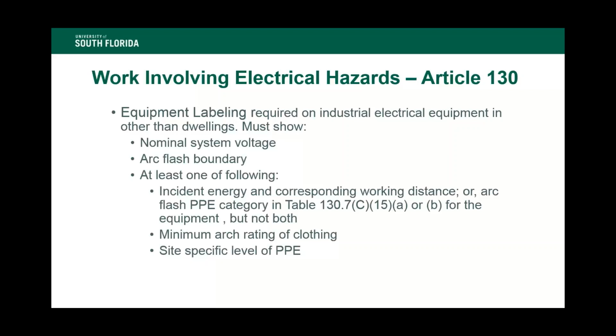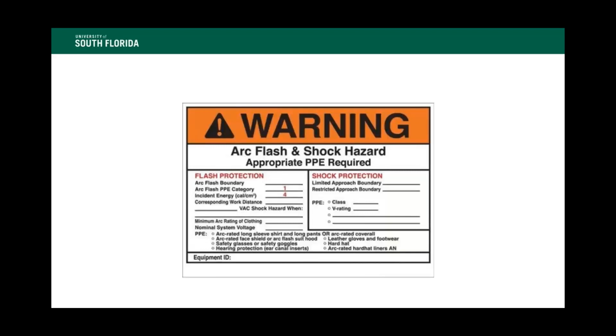So we also have a requirement for labeling equipment. While again, this is not enforced by OSHA, it is strongly recommended. A typical label is going to indicate the nominal system voltage, the arc flash boundary, as well as one of the following: either the incident energy and its corresponding working distance, or its arc flash PPE category, one or the other of these two, but not both. It's also going to show the minimum arc rating of clothing or site-specific PPE. Here's a sample picture of one of the many types of labels. There's no required format, but it must convey all of that information.